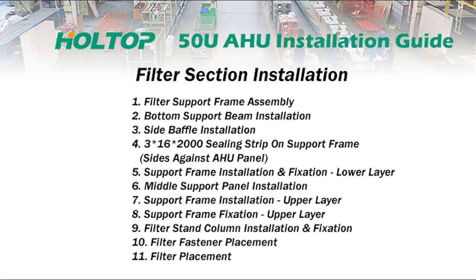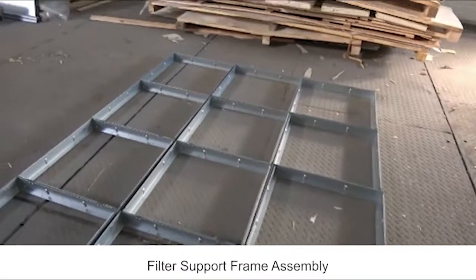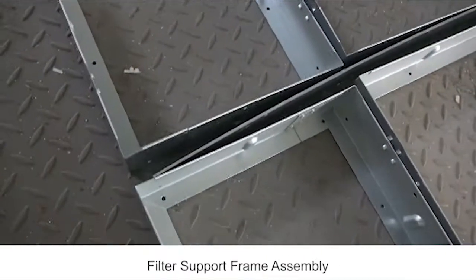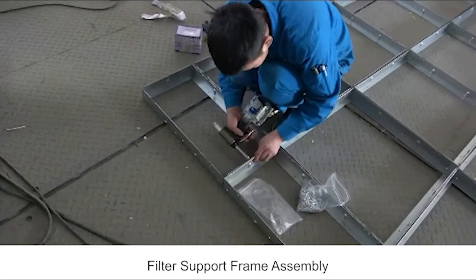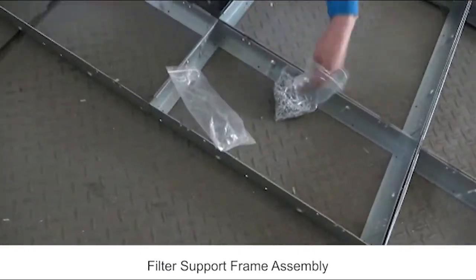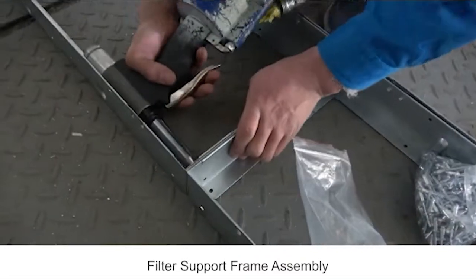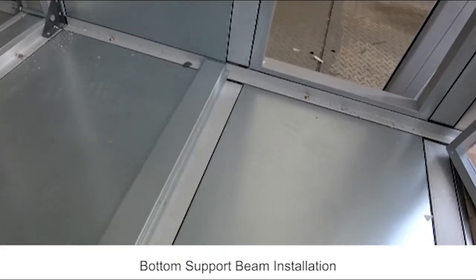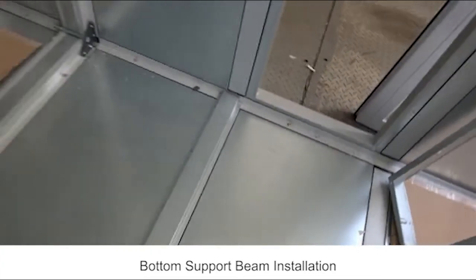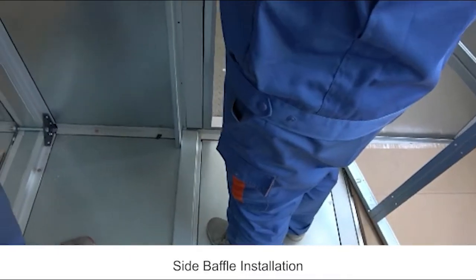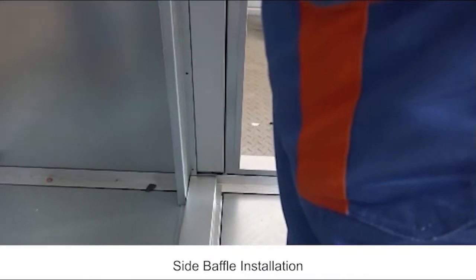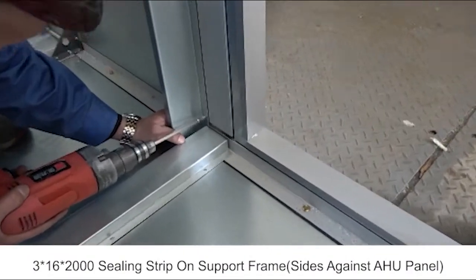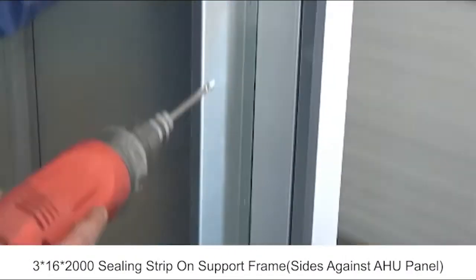Guideline for filter section installation. First, is the filter support frame assembly. Secondly, bottom support beam installation. Thirdly, side baffle installation. Next, sealing strip on support frame for the sides against AHU panel.